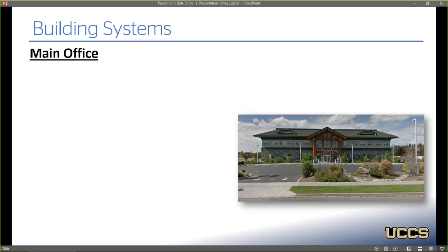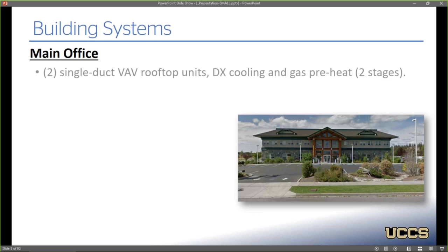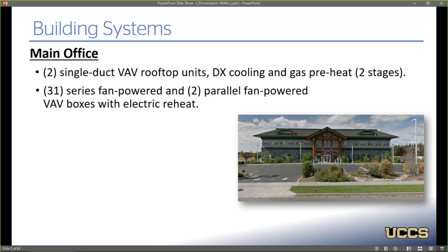So looking at the building systems, at the main office, it's primarily served by 2 single-duct VAV rooftop units with DX cooling and gas preheat. Each unit has 2 stages of heating and 2 stages of cooling, which is admittedly not great for temperature control. Downstream of those units are a number of series and parallel fan-powered VAV boxes with electric reheat, and those boxes have single-stage electric heat, which again is not ideal because it's either full on or full off.